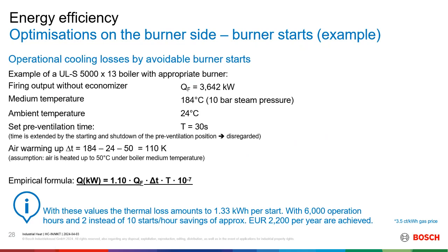Take for example, you're running a 10-bar steam system. The temperature inside the boiler will be around 184 degrees. The ambient temperature will be around 24 degrees, and you have a pre-purge, a ventilation process, of around 30 seconds. We assume around 50 degrees temperature gain by the time the air actually gets into the combustion chamber. If you just plug this into the heat transfer equation, you get this: just by reducing the number of start-stops from 10 an hour to around 2, you save around 2,200 euros per year.